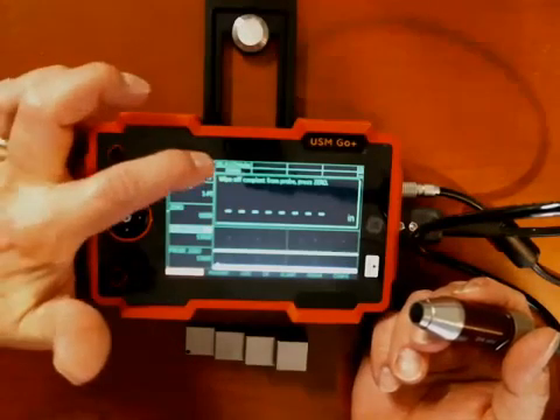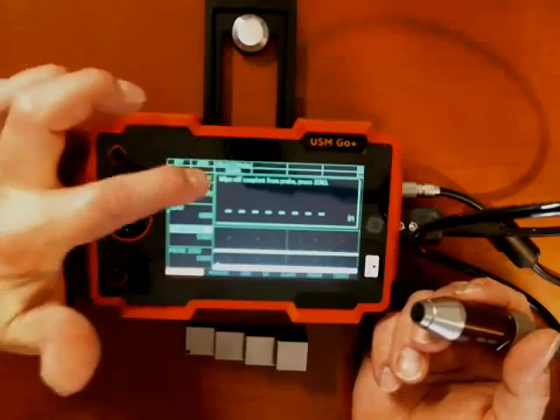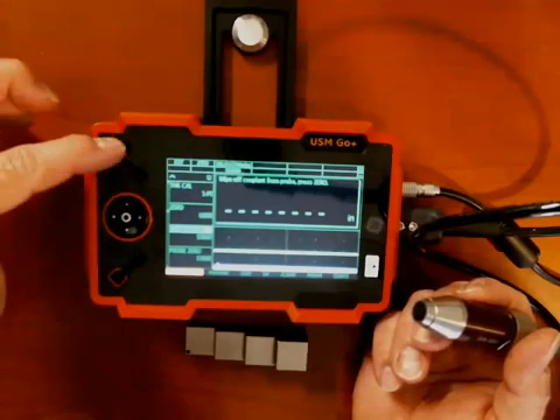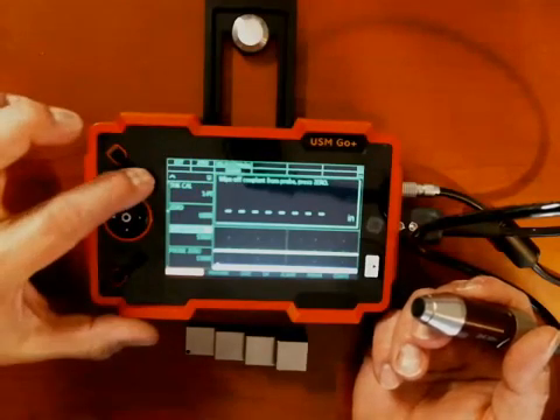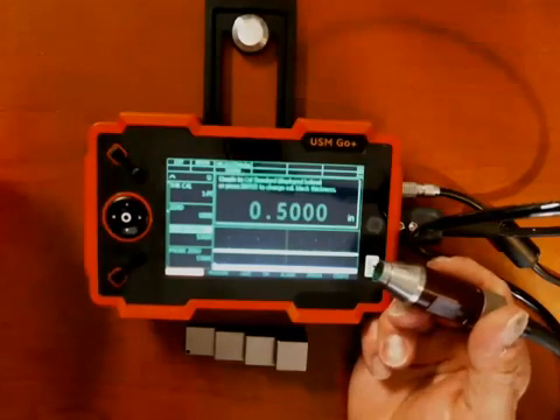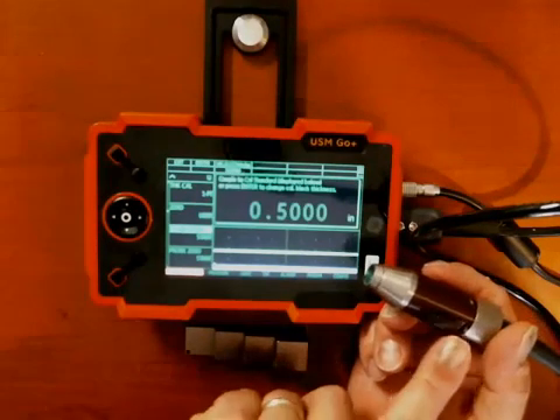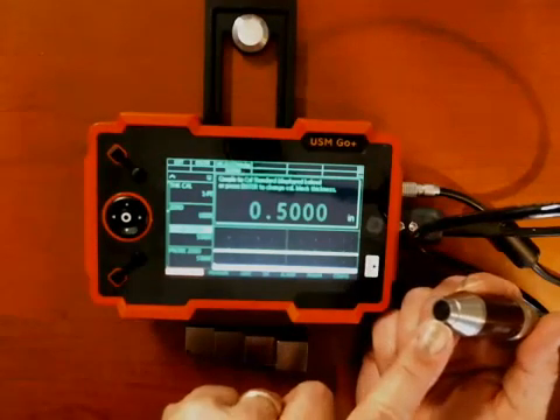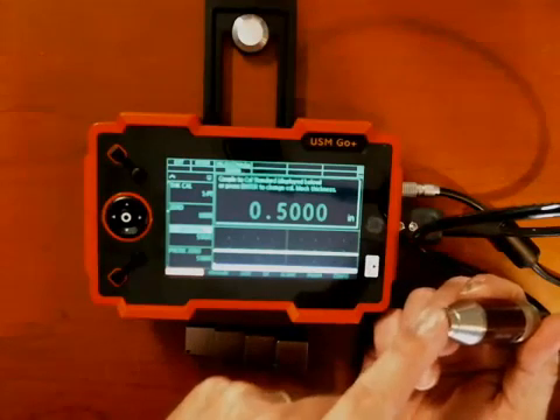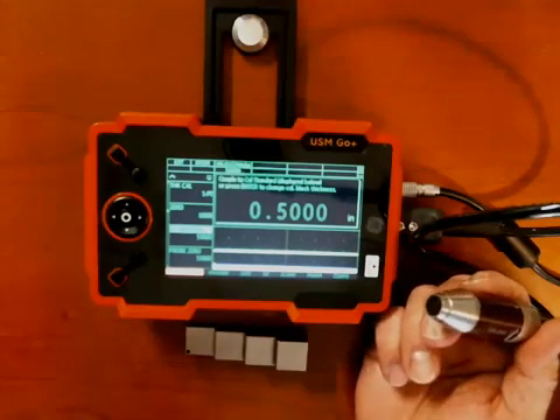Again, look up here at these 4 function keys, definitions in this upper left corner. I have exit and 0. So I press 0. And what the instrument just did was looked at the length of the delay tip, figure out where the tip of the probe is, and calls that 0.